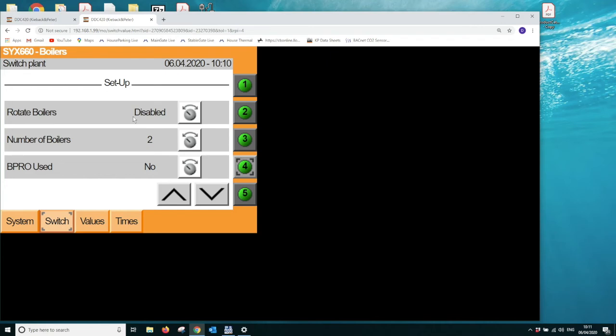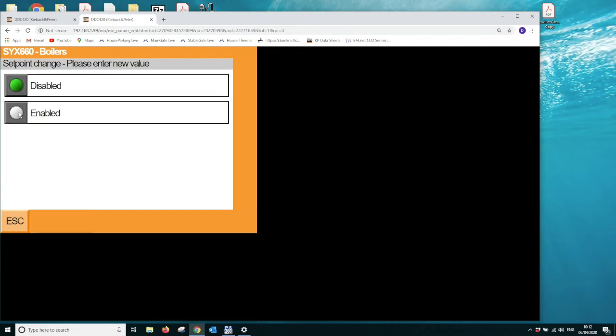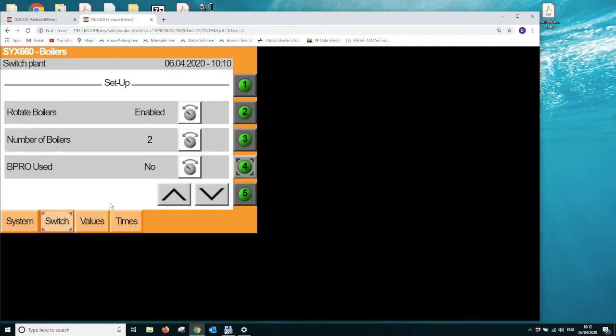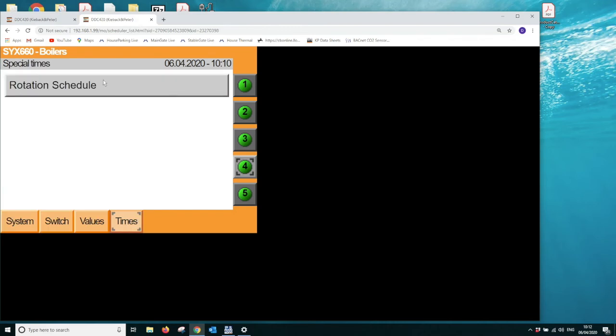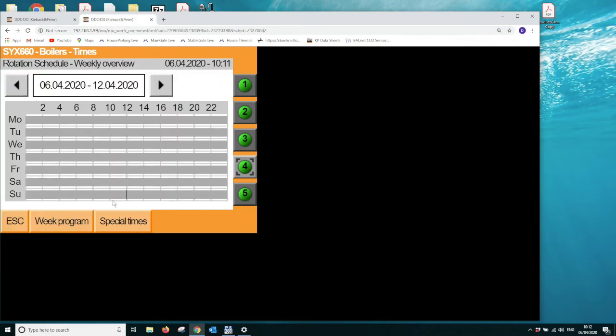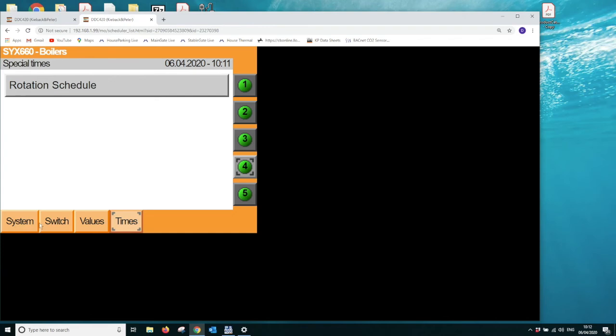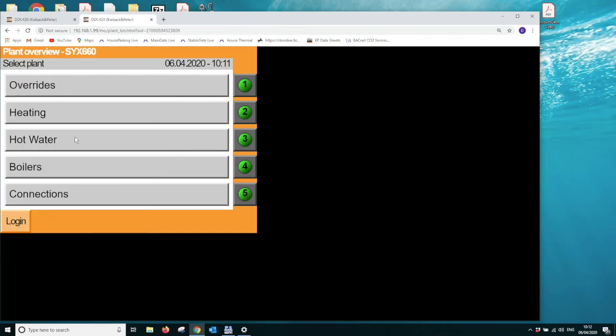If you do not wish to rotate the boilers on a weekly basis, you can leave that as disabled, but if you do, we can set them up as enabled. There's a time schedule which is pre-programmed into the system, which is set to rotate at midday on a Sunday. You can set up additional times for that, but the default is fine for now. We just go back onto system and choose boilers.